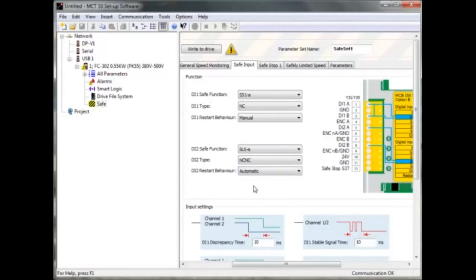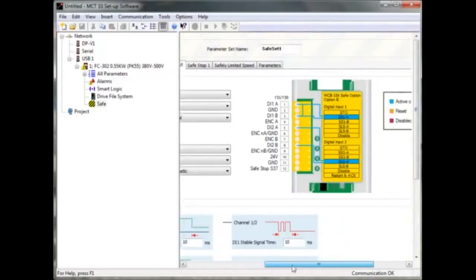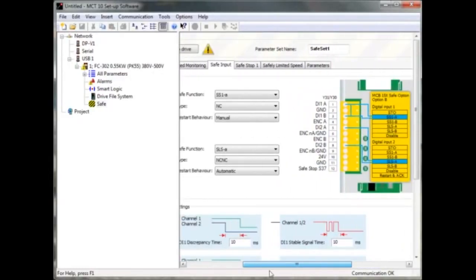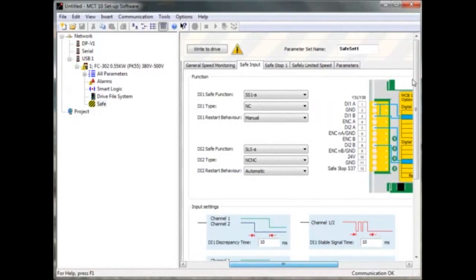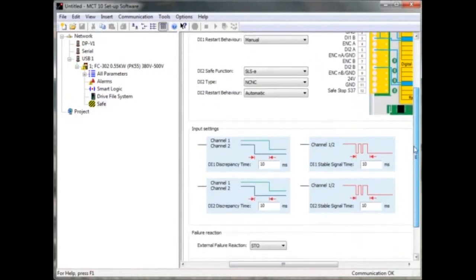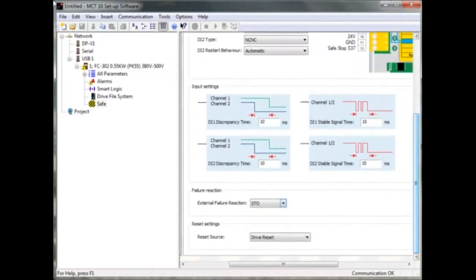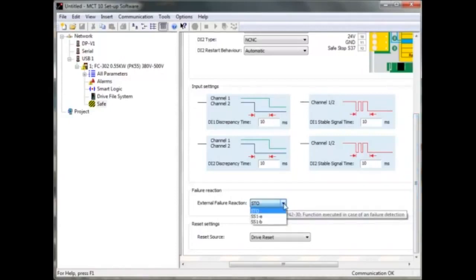On input settings, the first time value is how fast the option shall react — for example, on a broken wire or missing signal. The next time is the reaction time from the component, for example how fast is its switching. Normally these times are fine to use. You also need to choose an external failure reaction: if there is an unexpected problem or settings are incorrect, it will execute the external failure reaction you choose. The reset source is also selected here.